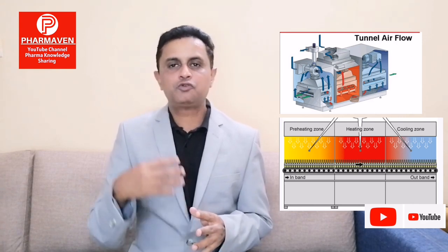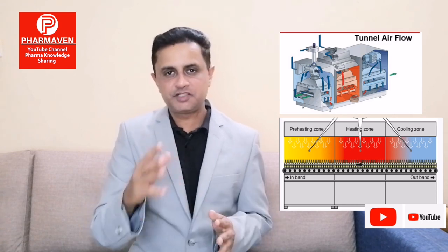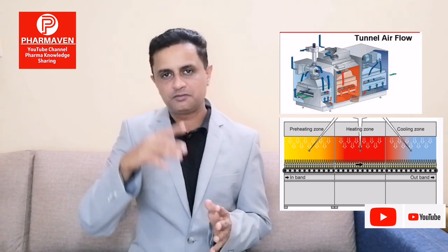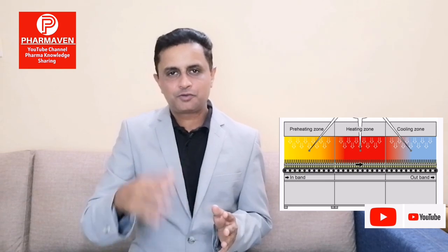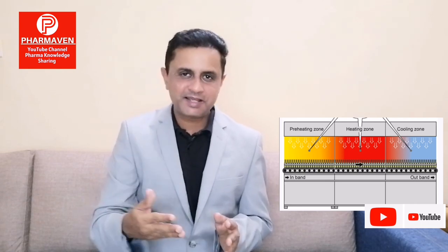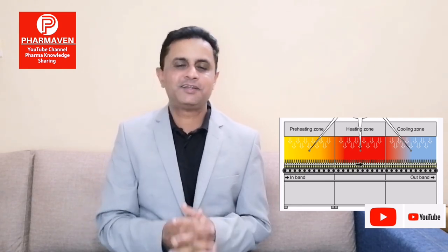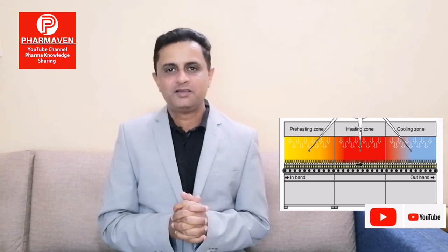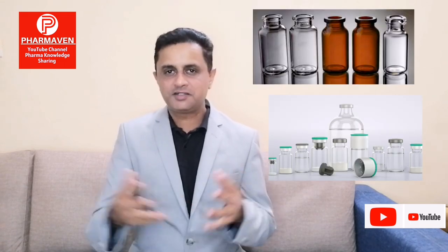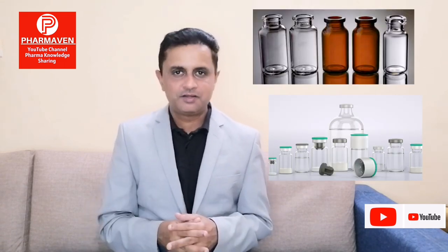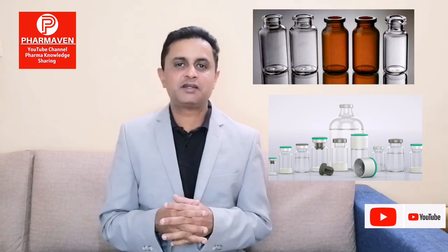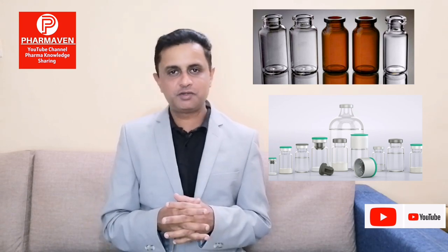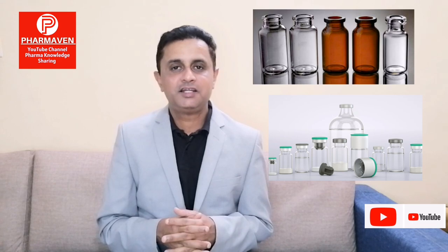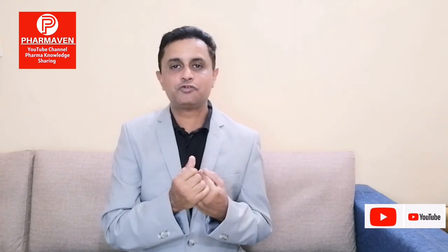Now how to qualify the tunnel? So this is the working principle of the tunnel. There is a blower which circulates the air through the heater bank. The heater bank heats the air and it transfers the heat to the containers. Now how can we qualify? When I have to qualify the tunnel, first I have to see how many containers there are for sterilization or depyrogenation. Practically all vial sizes and all container sizes should be considered, but in general there are three ways to look at it.